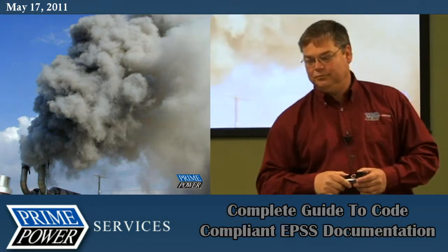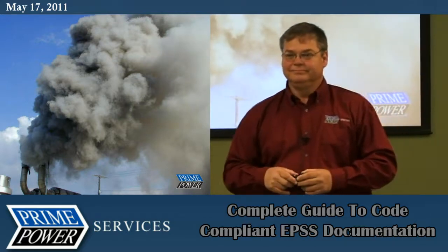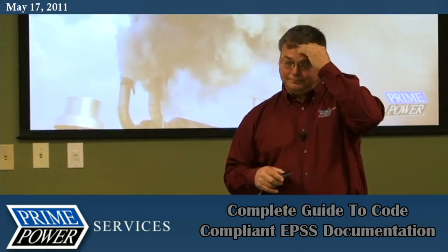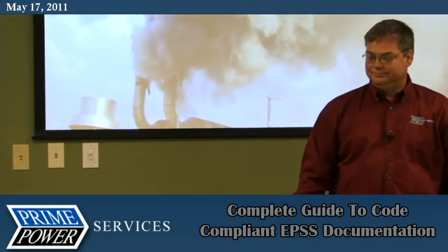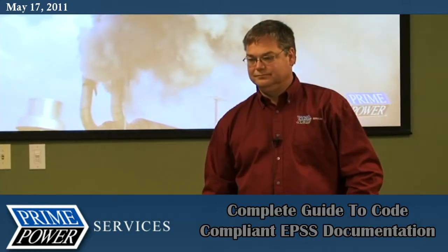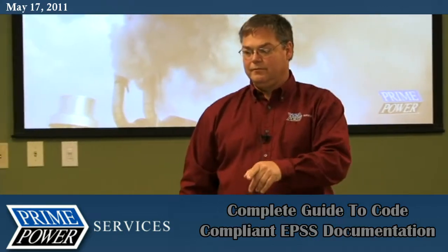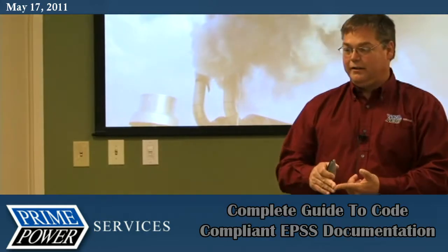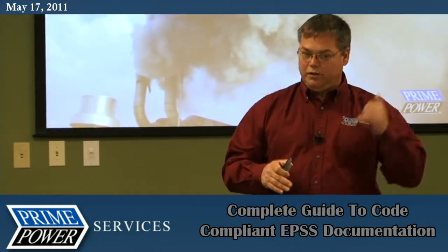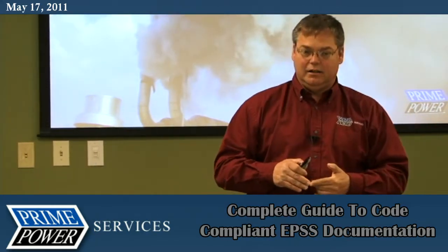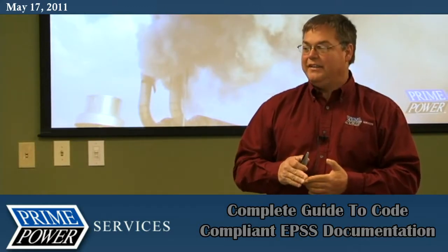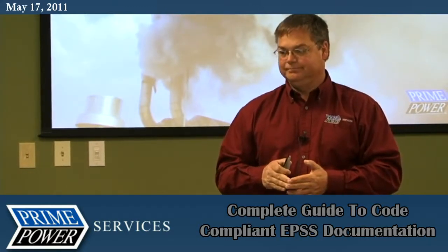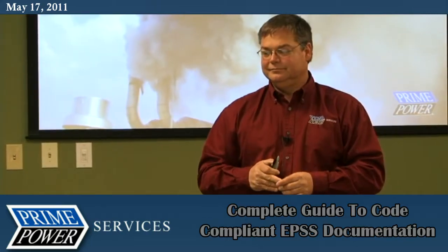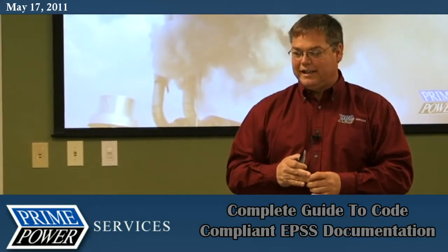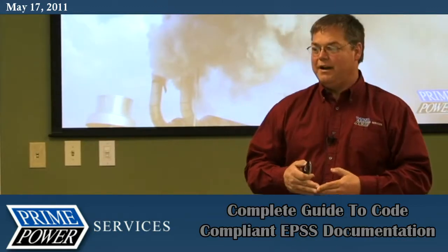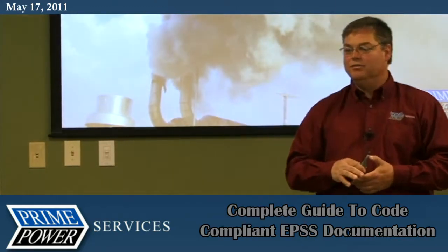So, switching to electric. Diesel fire - like you said a minute ago, NFPA 110 says you've got a monthly 30-minute run on load, as long as it's above 30%. Right, they want you to run it at 30%. For a generator, NFPA says - and I'll actually show you the code in a minute - monthly, for 30 minutes, at 30% load. If your load's greater, that's even better. If your load's less, there are some nuances you can get around with running it for less time, and that's when you've got to run the load banks and all that.